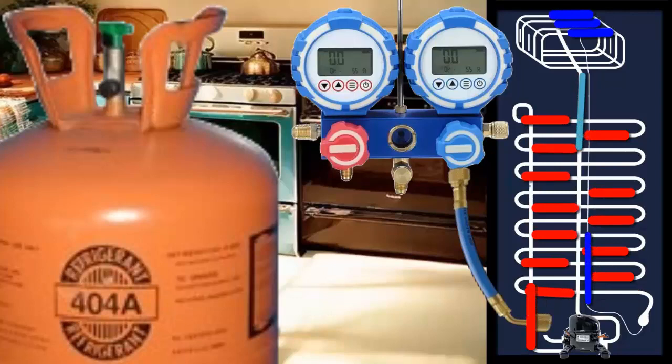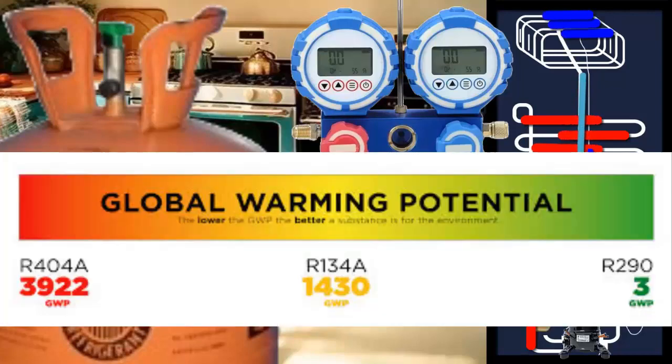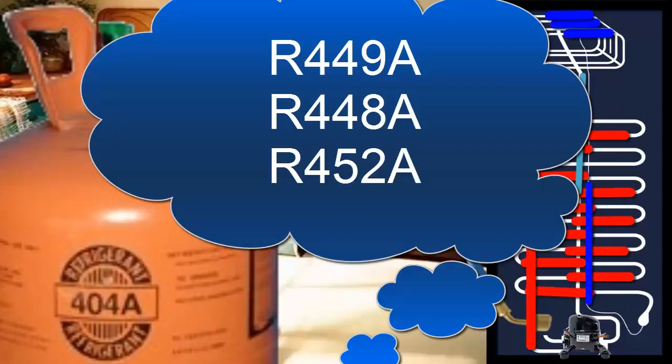The main drawback of R404A is its high global warming potential, close to 3922, which is why it is subject to ecological environmental restrictions. Currently, the most common replacement gases for R404A in equipment that is already in operation are R448A, R452A, and R449A.